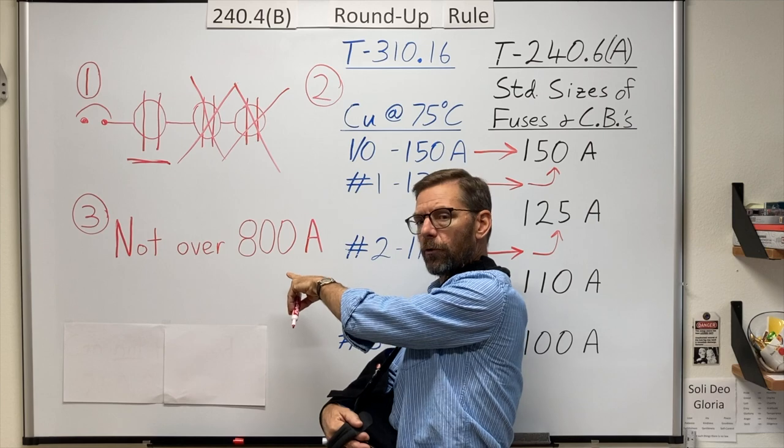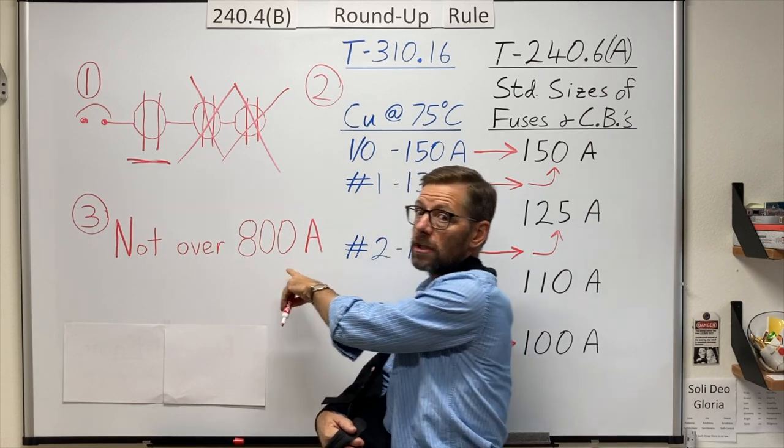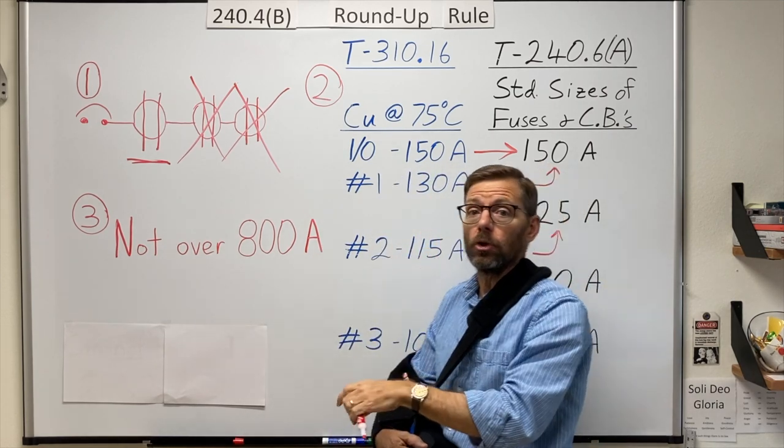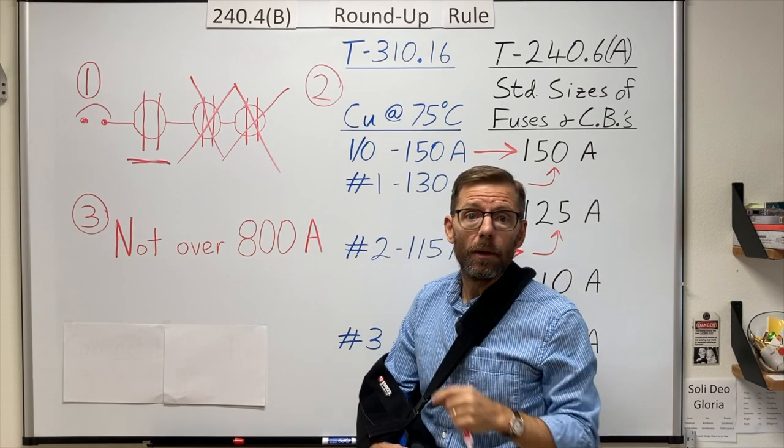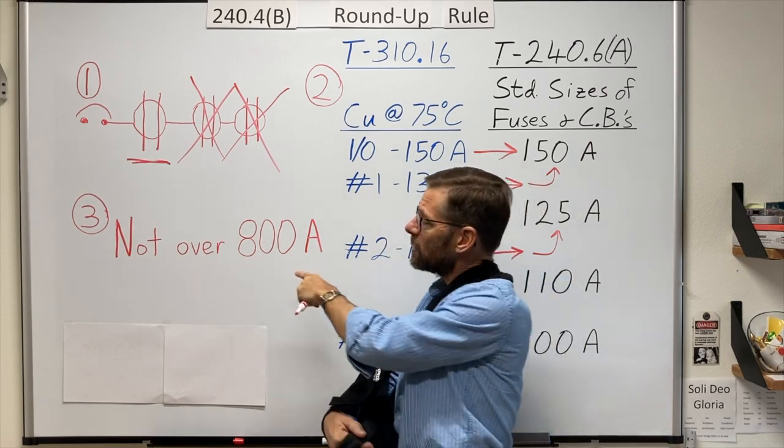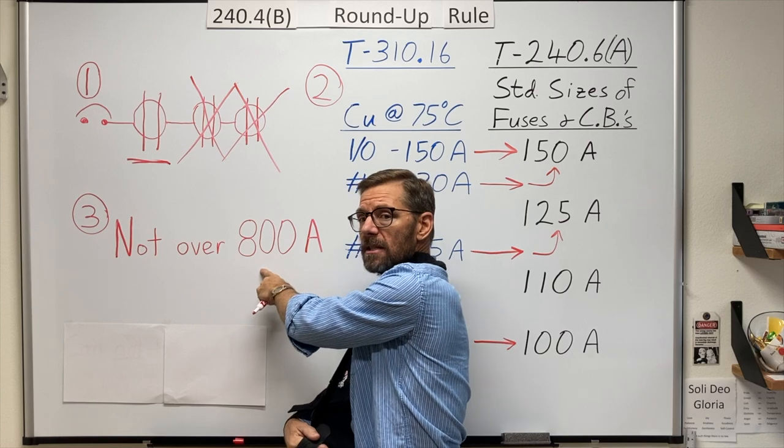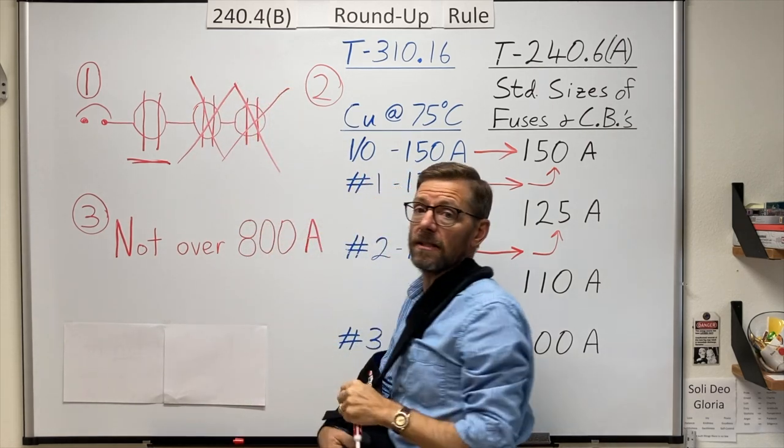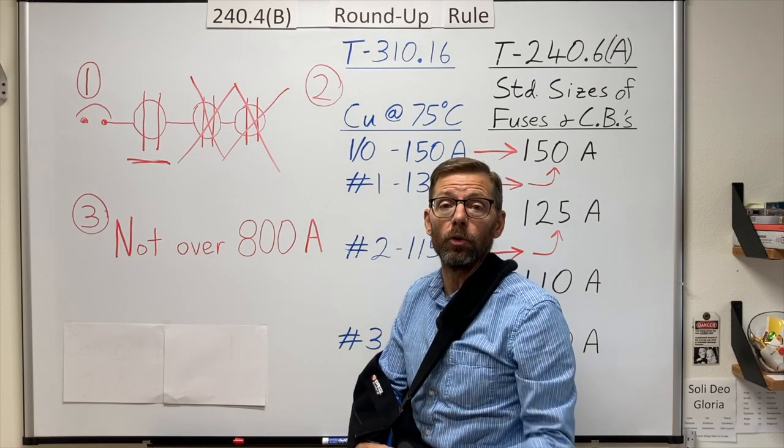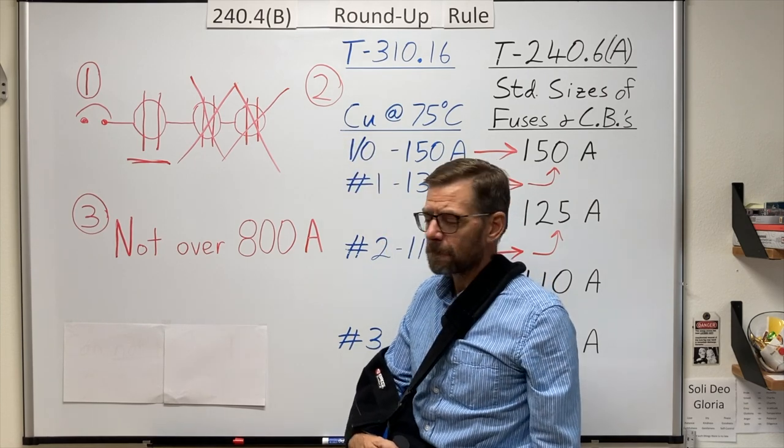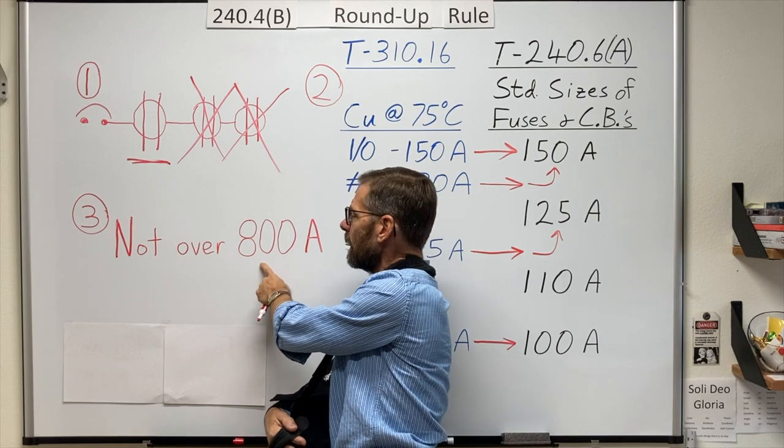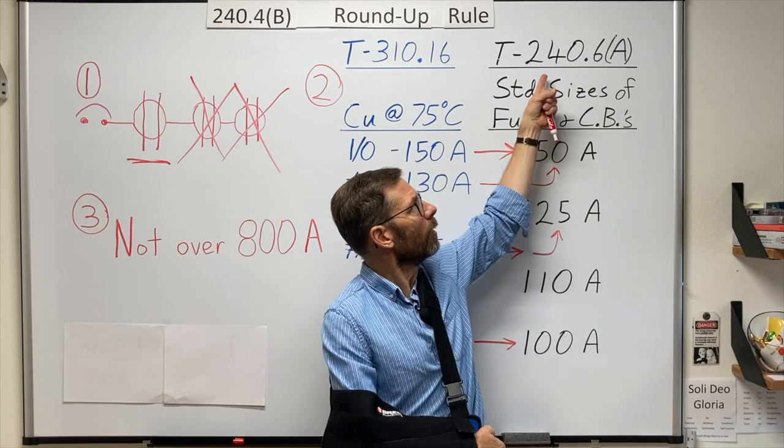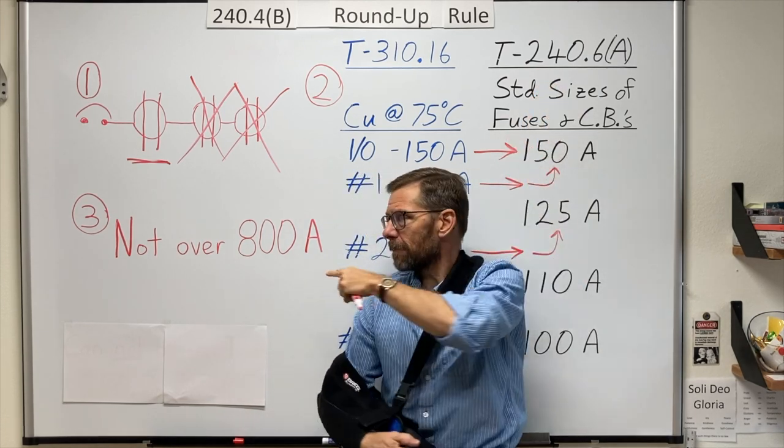Condition number three says I can use this provision up to and including 800 amps, but not above. Incidentally, that pretty much says the same thing as 240.4C says as you read down through the various subsections.